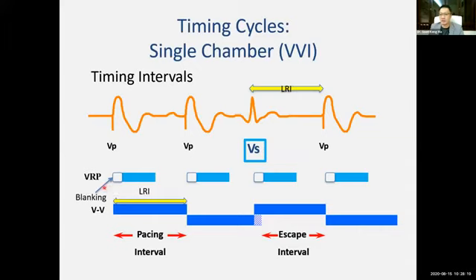One is called the blanking period here. And another one, in blue here, is called the refractory period. What are these? Why are they there? Now imagine if you miniaturize yourself and go into the cardiac chamber and be looking at that pacing lead. When it paces, it's like a flashlight shining in your face, blinding you. You couldn't see. It's better for you not to see because it's a very blinding flash. It's like the whole area in that cardiac chamber is being filled with thunderstorm or flashlights. So if so, then you better have a blanking period. If not, then you will saturate your sensor up to a level that for it to recover, it may cause a problem.